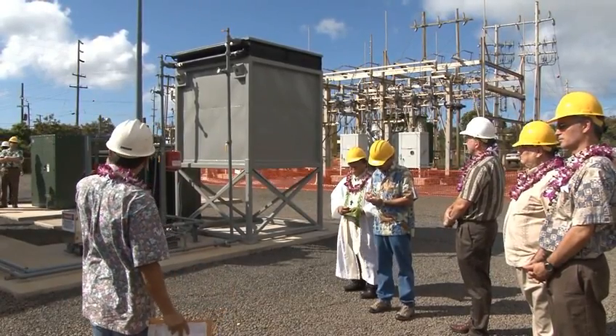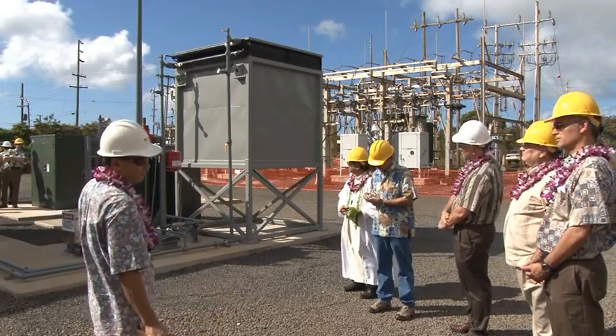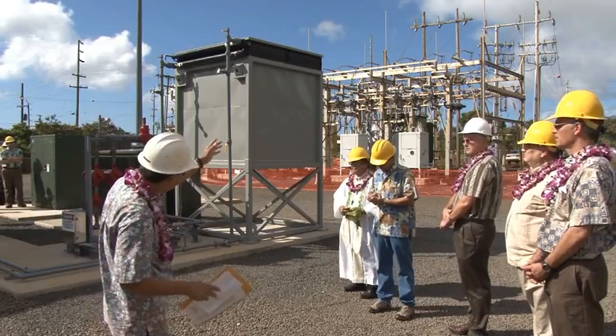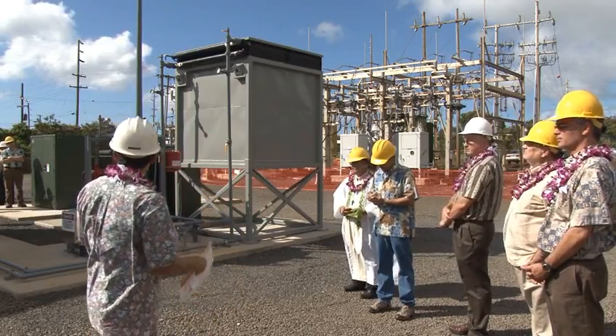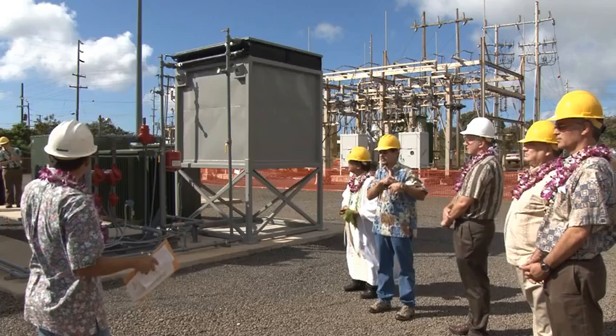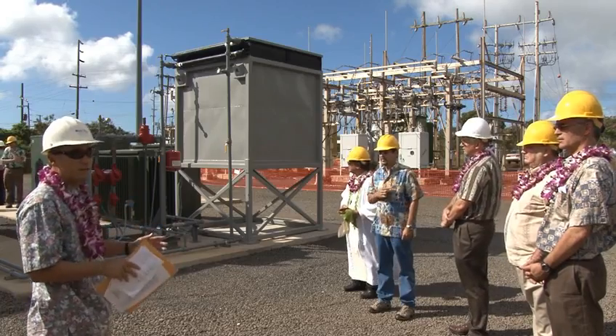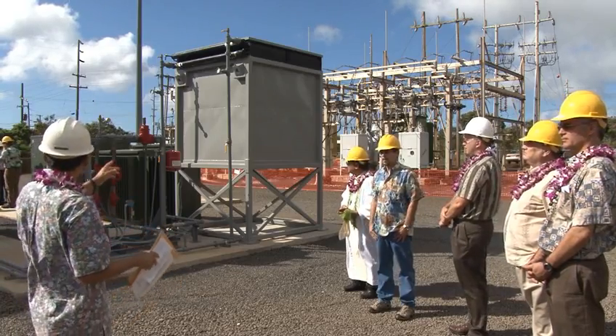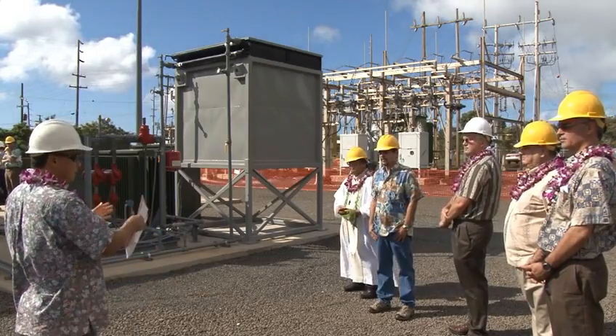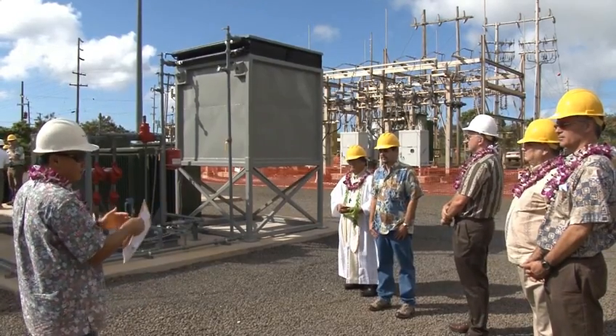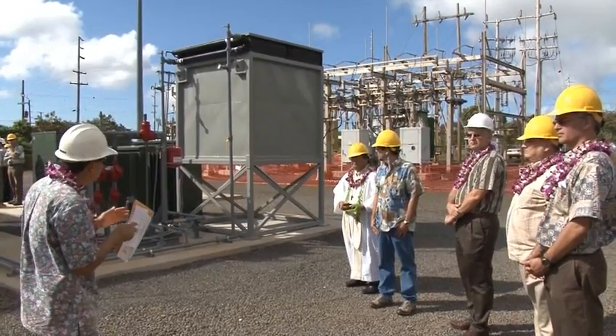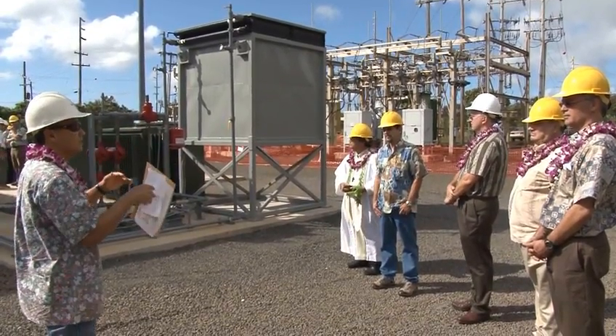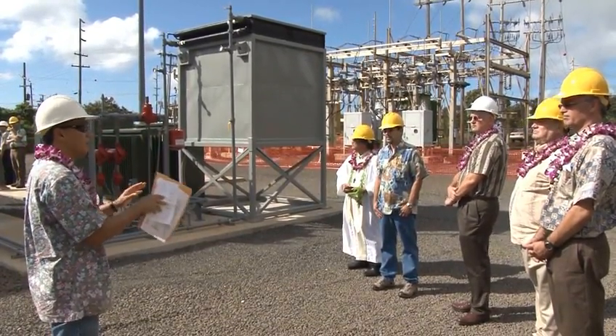And the compartment right next to it is our switch gear. It's a four-way switch gear that takes the two incoming feeds from the station. It takes a feed from the transformer, from the battery, and it also has a spare feed for the PV. So the PV is actually going to be coming into the switch gear with the battery, and that's how they're going to monitor each other. And whatever is coming out to the bus is the net sum of the battery and the PV working together out there.